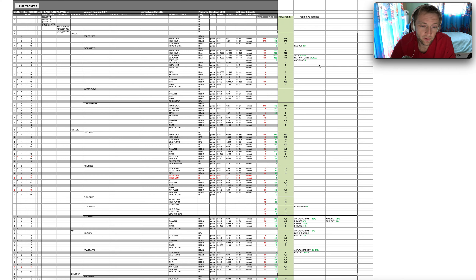If you have air suction, you will have higher oxygen content and will try to adjust the boiler by adding more fuel to reduce it — but that will make things worse, and your oxygen analyzer filters will become dirty. You must find a way to make good inert gas with lower smoke density in the exhaust gases. With the latest fuels on board, exhaust gases should be crystal clear. Engineers should also check the gases exposed to atmosphere at berth or anchorage, as NOx and SOx levels can now be measured by drones.